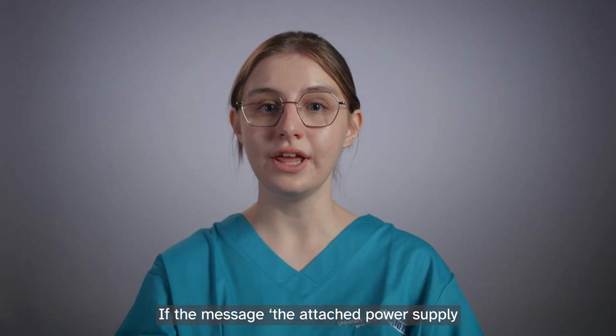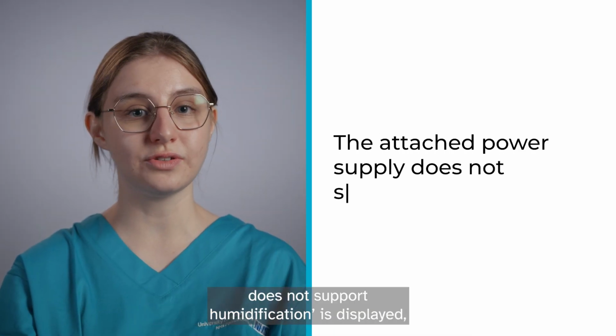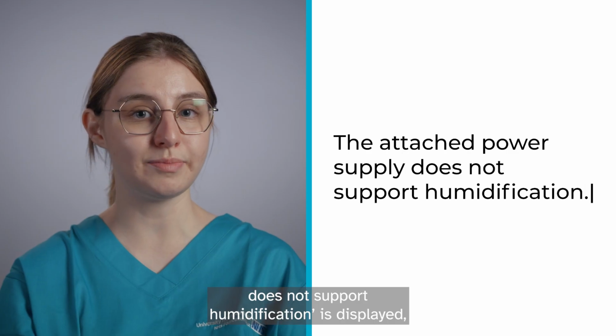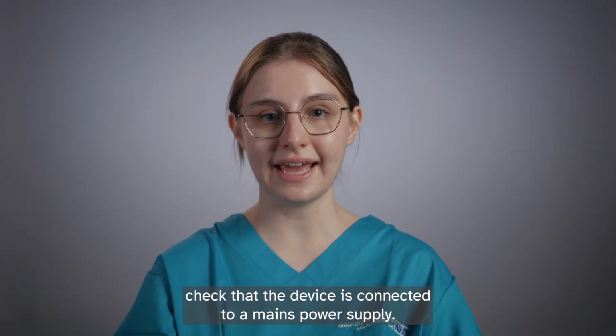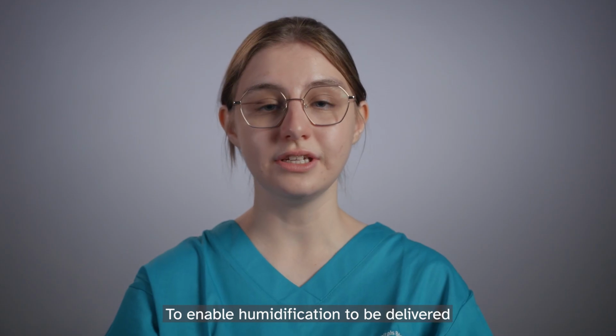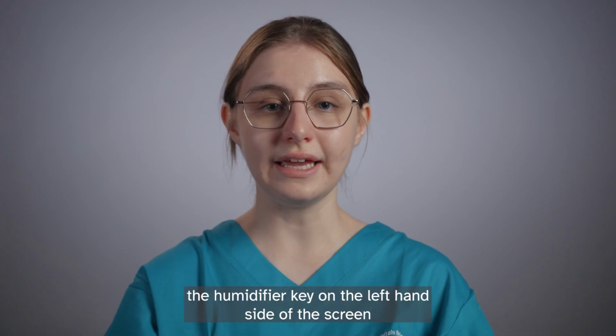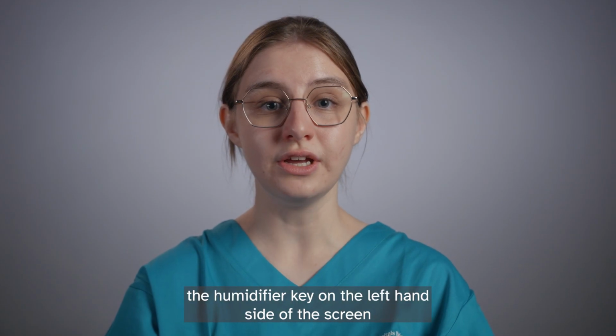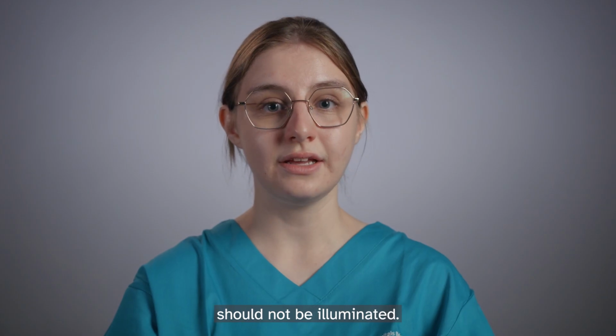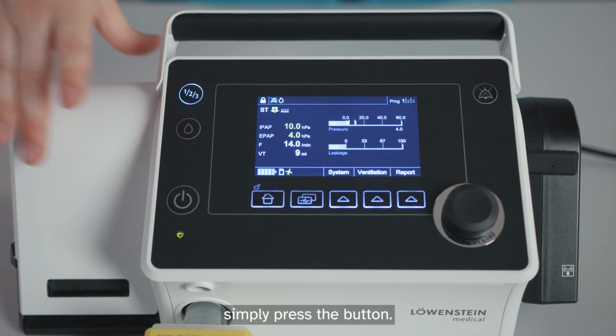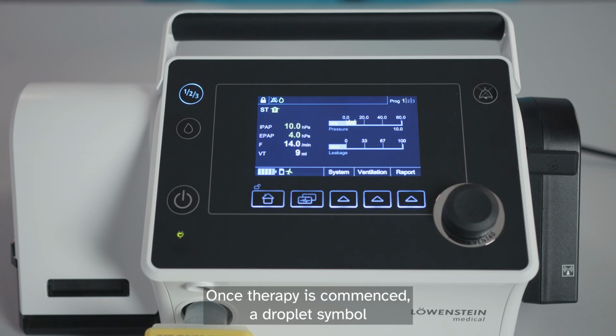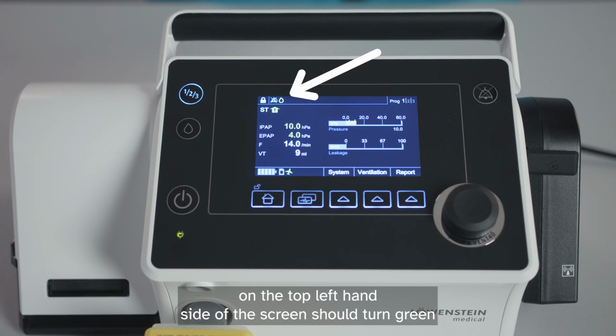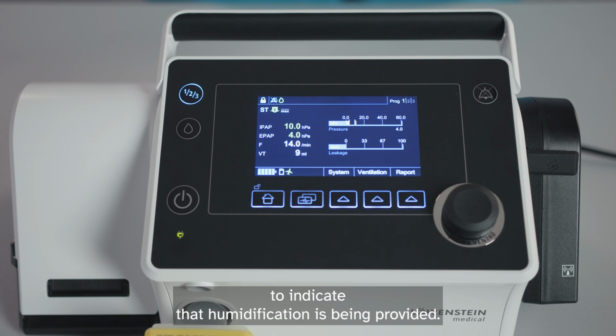If the message, "The attached power supply does not support humidification," is displayed, check that the device is connected to a mains power supply. To enable humidification to be delivered, the humidifier key on the left-hand side of the screen should be illuminated. To switch off, simply press the button. Once therapy is commenced, a droplet symbol on the top left-hand side of the screen should turn green to indicate that humidification is being provided.